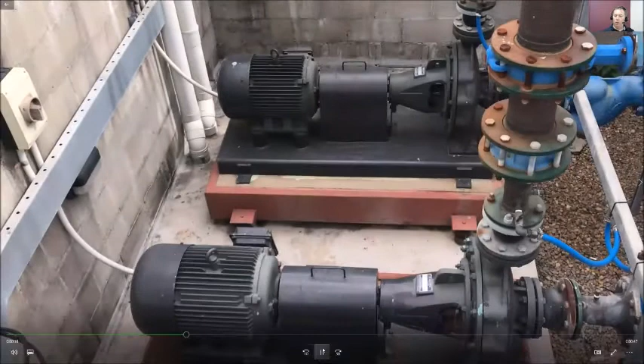And here are the condenser water pumps. The thing to note is that it operates 24/7, irrespective of the weather, who's in the building, what year, or what time of day - this thing is going flat out 24 hours a day. Not only is it going flat out, but most of this equipment is oversized by 40%. To reduce the output, they use valves to throttle the performance and restrict the flow - so there's flow restriction as well. These are major energy consumers going flat out.